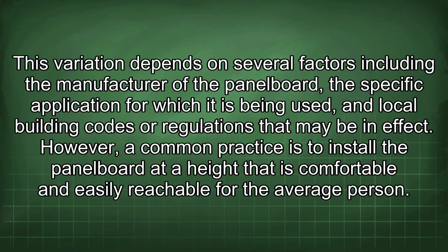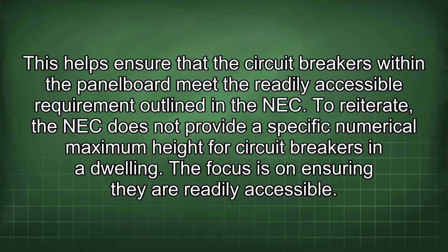However, a common practice is to install the panel board at a height that is comfortable and easily reachable for the average person. This helps ensure that the circuit breakers within the panel board meet the readily accessible requirement outlined in the NEC. To reiterate, the NEC does not provide a specific numerical maximum height for circuit breakers in a dwelling. The focus is on ensuring they are readily accessible.